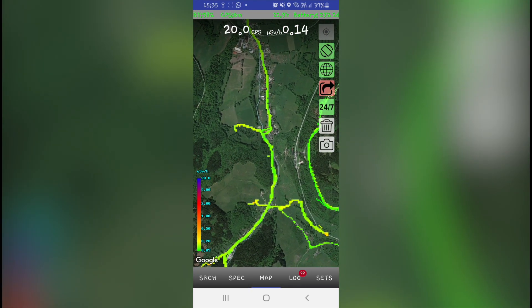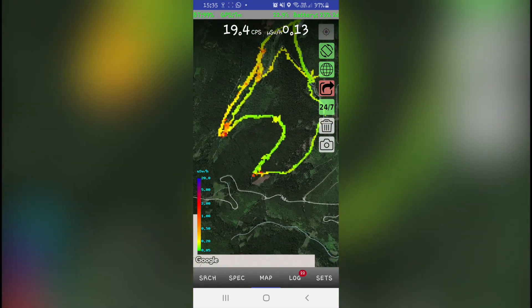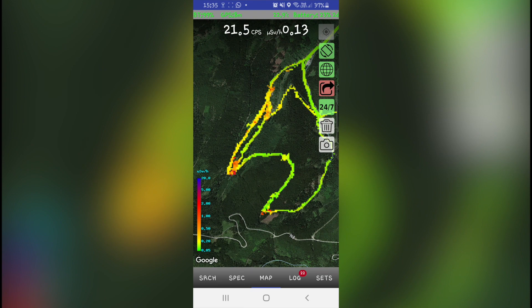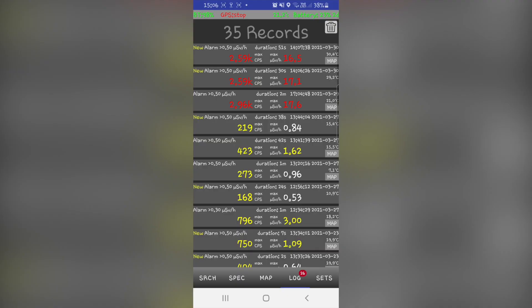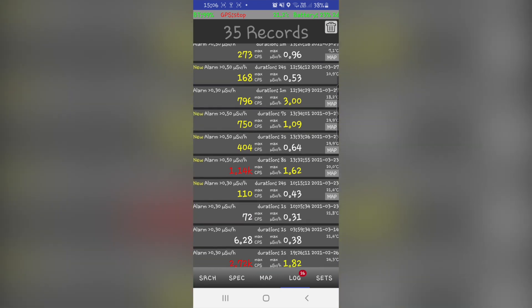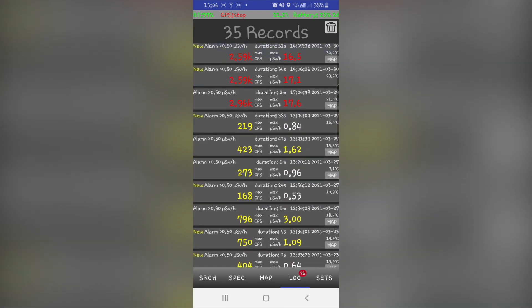Since Radiacode is so small, it's very portable and you can take it anywhere you want. What's even better is that it automatically makes a map of background radiation anywhere you go. A CPS or dose alarm can be set in the Settings tab, and when an alarm is triggered, it will be saved in the Log tab.